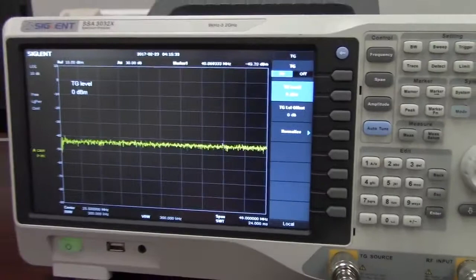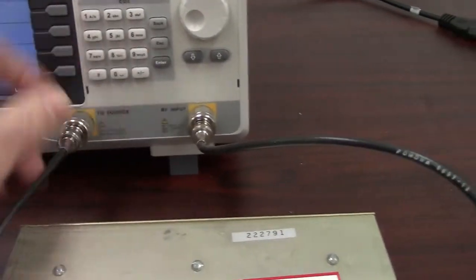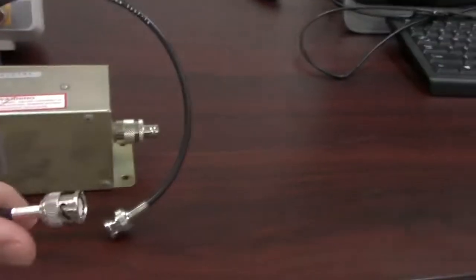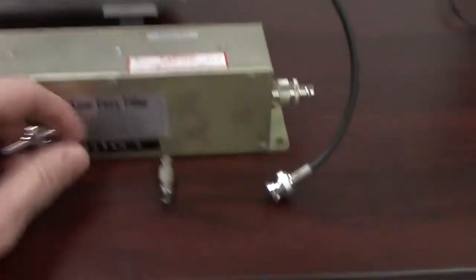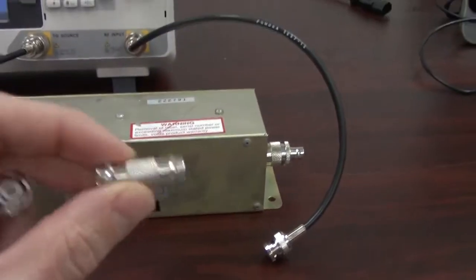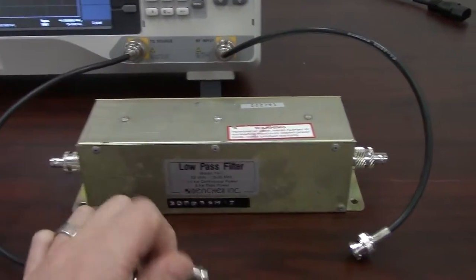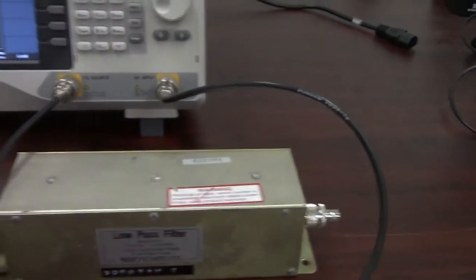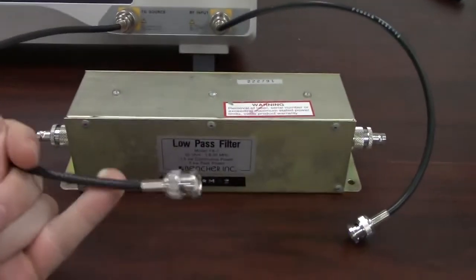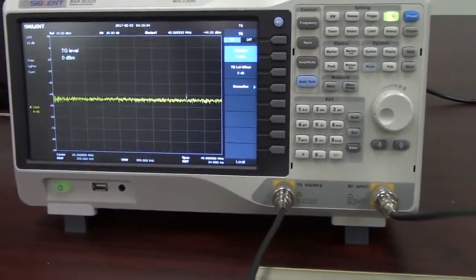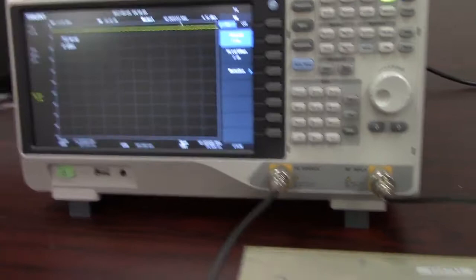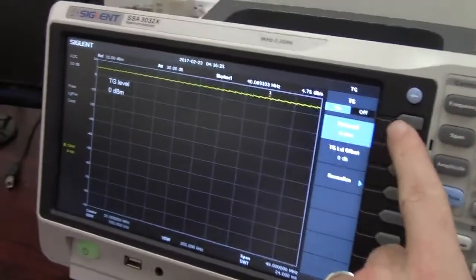And first step is going to be normalizing. So, you'll see I have two adapters as well and two cables here, two BNC cables. And I've got a BNC barrel. The BNC barrel, we're going to be able to calibrate. So, normalizing, we're going to be able to remove the reflection and absorption effects of the cabling by doing the normalization process. Just one second, I'm going to put this barrel in and be right back.